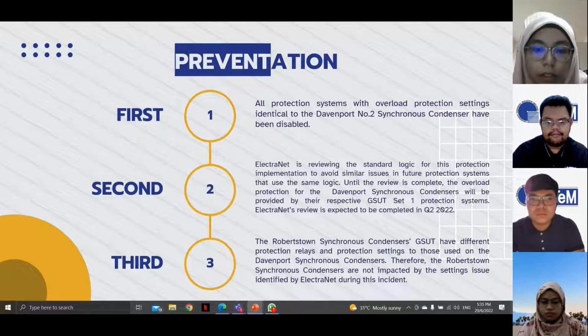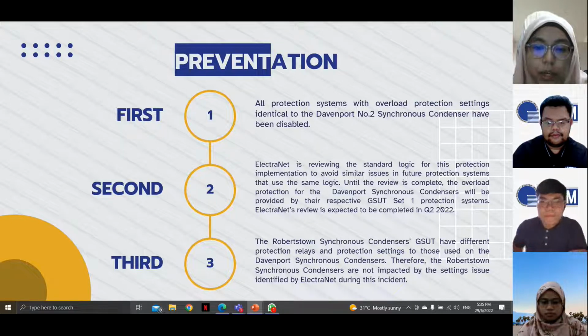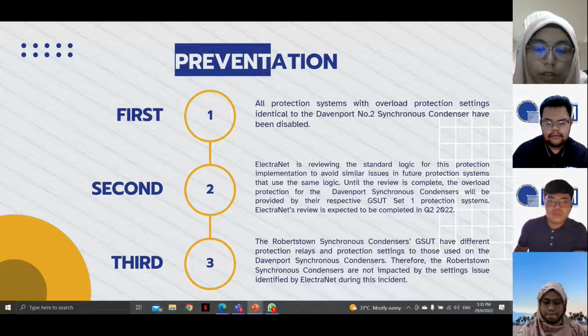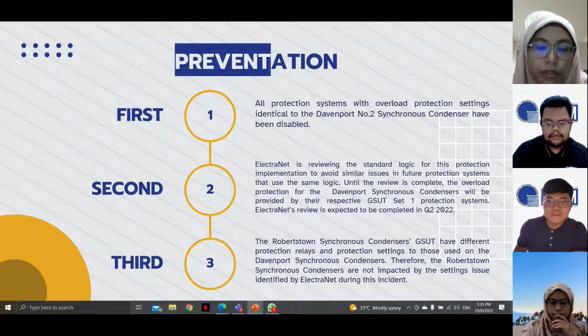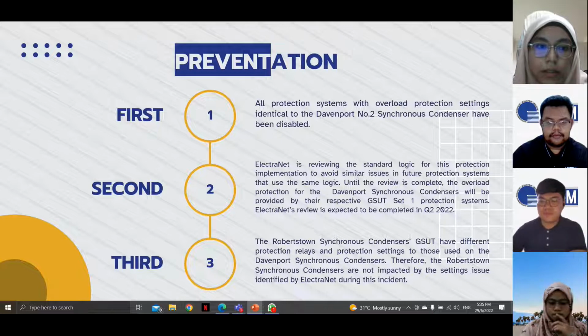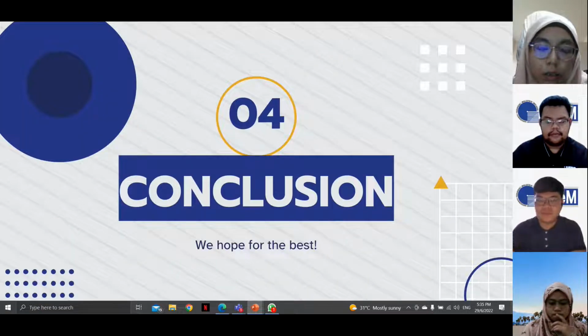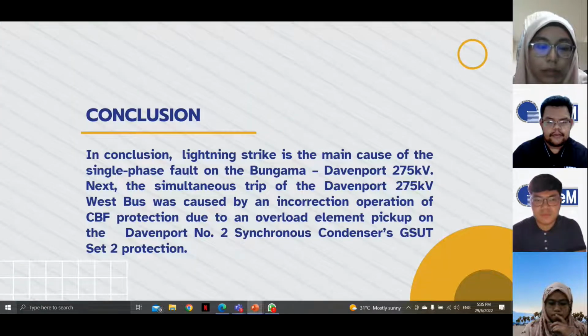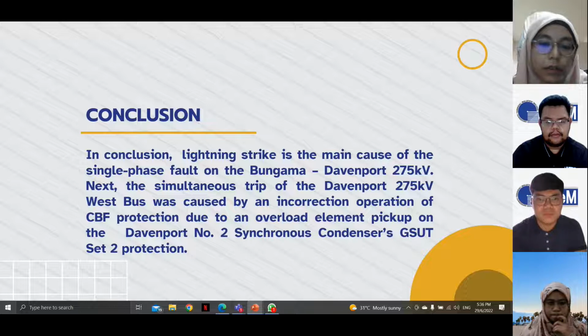Third, the Robertstown synchronous condenser GSUT has a different protection relay and protection setting to those used on the Davenport synchronous condenser. Therefore, the Robertson synchronous condensers are not impacted by the setting issue identified by Electranet during the accident. Next. Okay, this is the conclusion for this accident. For this conclusion, lightning strike is the main cause of the single phase fault on the Bungama - Davenport 275 kilovolt line.